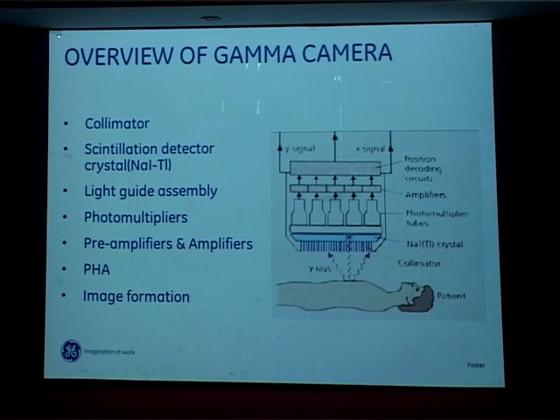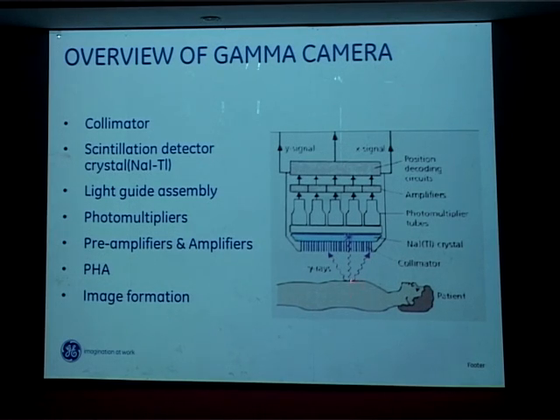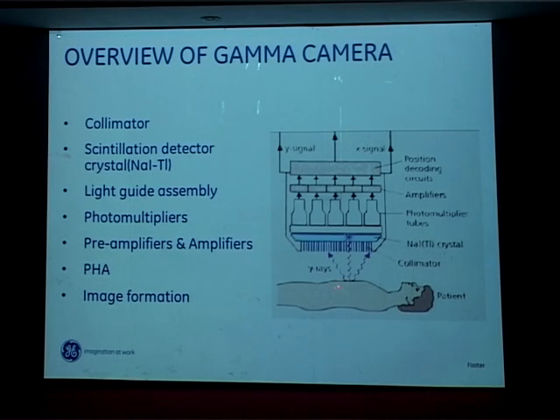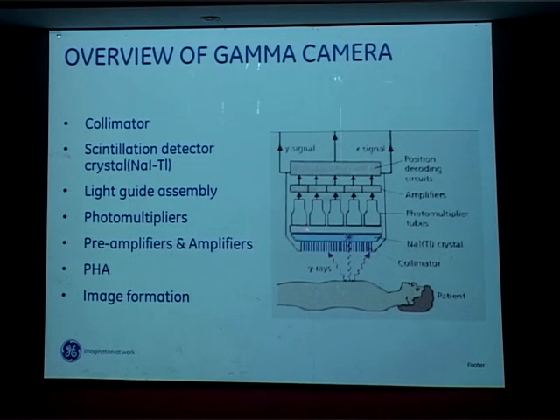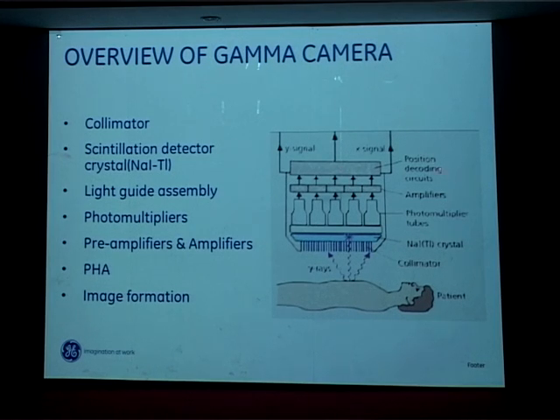The components of a gamma camera: a patient is injected with a gamma-emitting radioisotope with a short half-life and energy anywhere between 140 to 200 keV, so the radiation burden for the patient is less. The emitted gamma rays are picked up by the gamma camera to form the image. The components are: a collimator, a scintillation detector crystal of sodium iodide doped with thallium, a light guide assembly, photomultiplier tubes, preamplifier and amplifier, pulse height analyzer, and finally image formation.